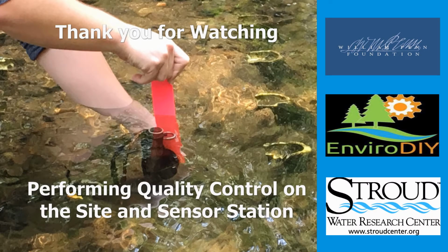This concludes the process on how to perform quality control or QC on the sensor station. At a minimum, this should be done quarterly or every 3 months. Remember to completely fill out the quality control sections of the field visit datasheet. This means recording all timestamps when QC was performed for a certain parameter and recording the sensor values that match with the timestamps. The QC instruments used in the sensor station sensors may not have the same value, but should produce values fairly close to each other. The process of QCing is more about monitoring sensor value drift and relative accuracy, rather than looking for direct matches between the field instruments and the sensors.